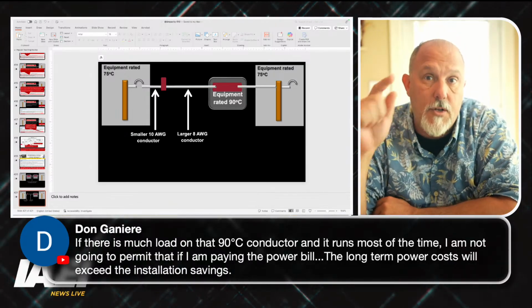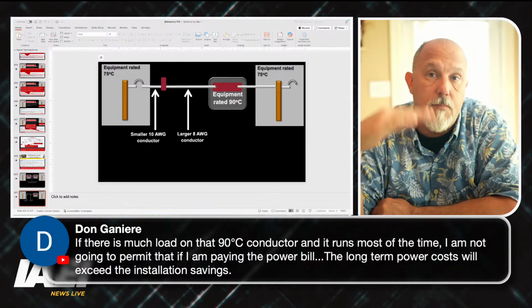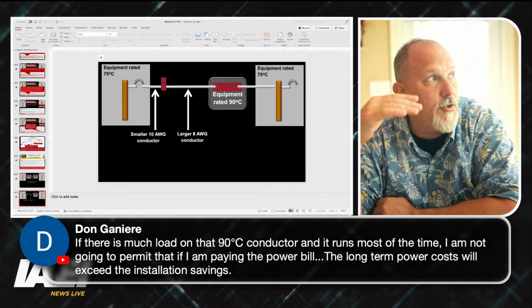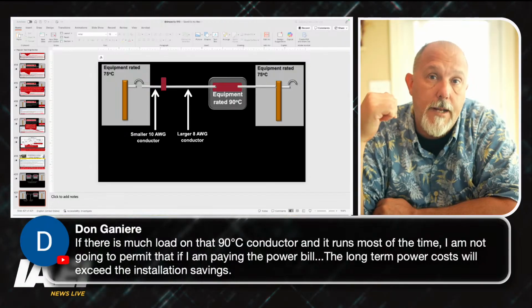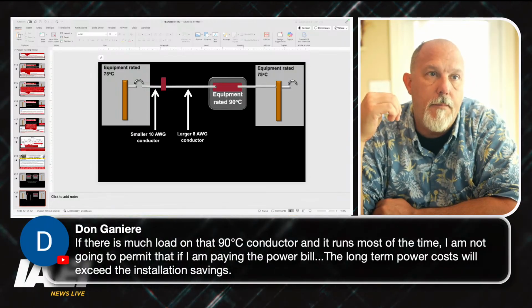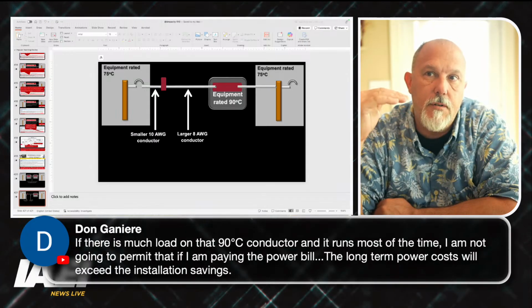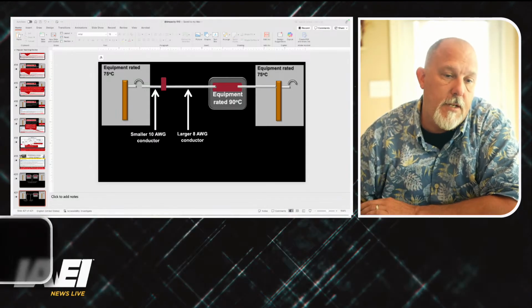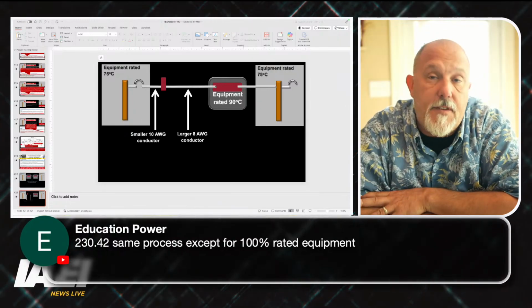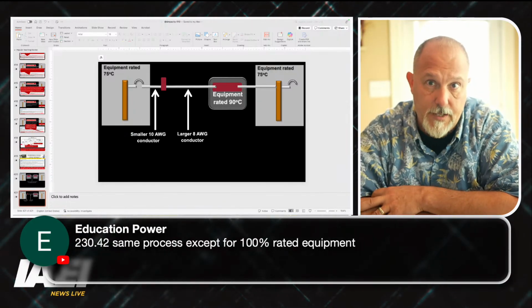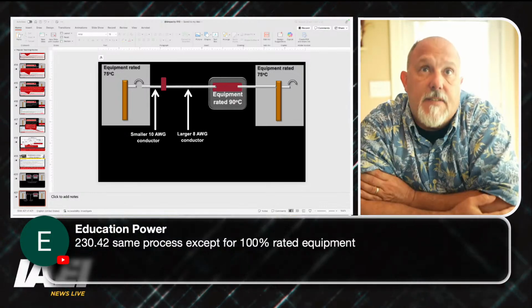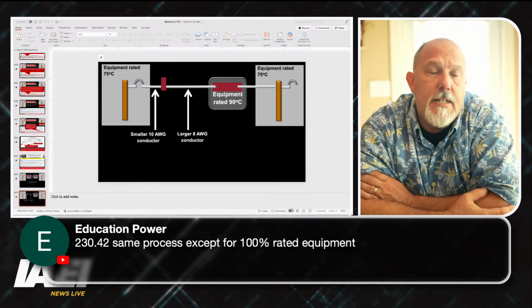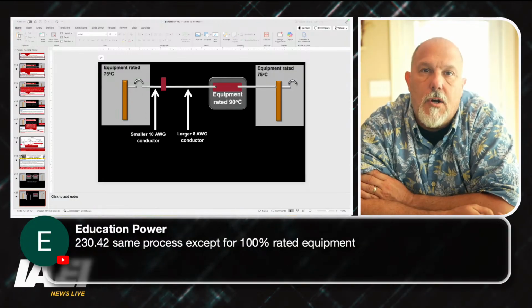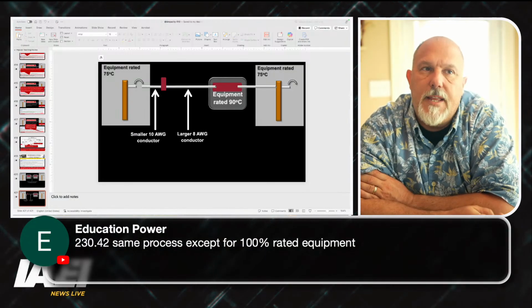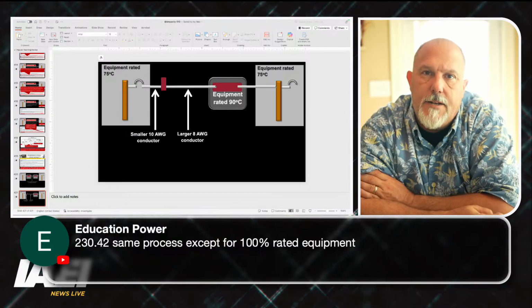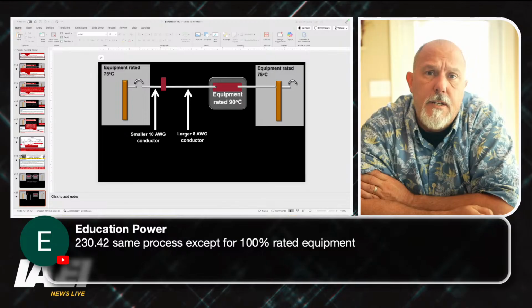And what Don is getting to is the fact that the smaller conductor is going to have a larger impedance, right? So that will cause I squared R losses. I've never done the math to know how much, like if I decrease the size of the conductor and I'm using it continuously, what's the dollars that translate into? I don't know what the additional heat loss is. I don't know if it's significant enough.